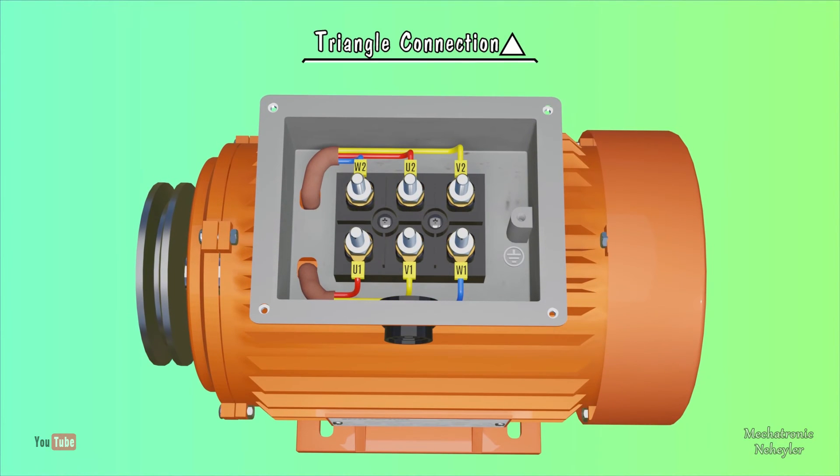We join terminals U1 and W2 using a metal plate. In the same way we join V1 and U2, and finally W1 and V2.